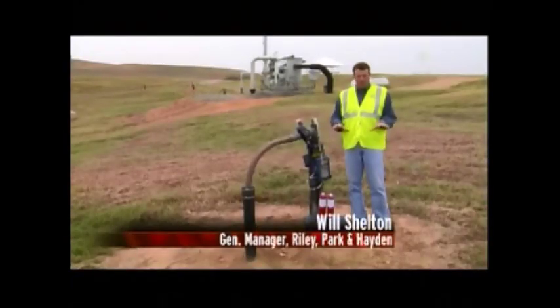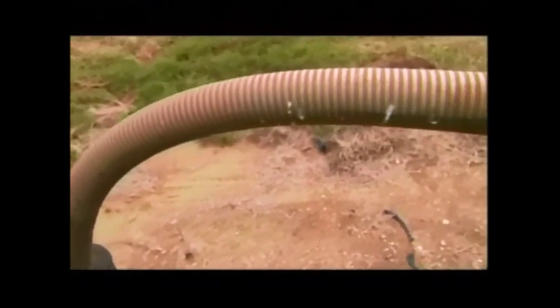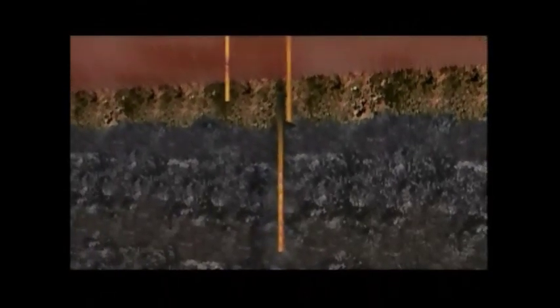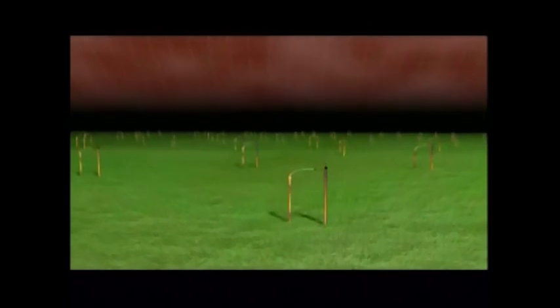What we're standing on top of is actually waste that's been buried at least five years or more, and we're standing on top of an active live gas well that's extracting methane out from the subsurface. 120 of these perforated wells, sunk between 65 and 135 feet into the garbage, pull up 5,000 cubic feet per minute of landfill gas — enough to heat 30,000 homes.